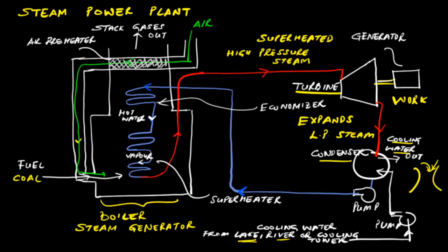In the condenser, the low pressure steam is fed in and the output is condensate. The pressure of this condensate is increased by a pump, enabling it to flow back into the boiler. In the boiler, the condensate is heated first in an economizer, which uses combustion products to heat the water, then the water vaporizes to high pressure steam. The air used for combustion is also preheated using exhaust gases in the air preheater, and eventually the exhaust gases are purified and released into the atmosphere.